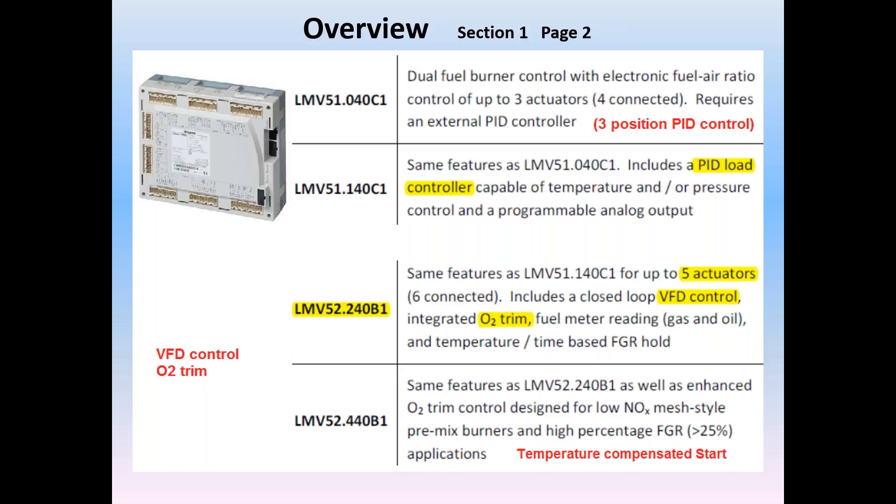Fourth and final is the LMV52440, which adds along with all of the above mentioned features, plus it includes a temperature compensated start. This feature was added for units that employ mesh style pre-mix burner heads. During pre-purge, the air temperature is measured, and the ignition settings are adjusted to compensate for the current temperature.